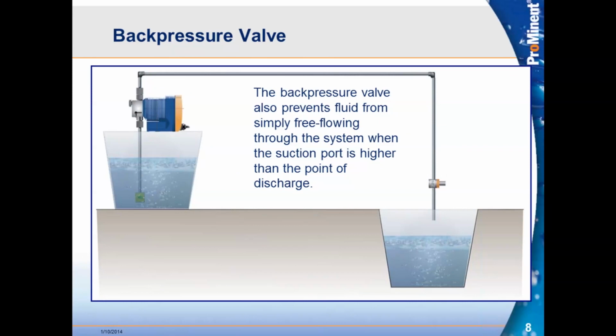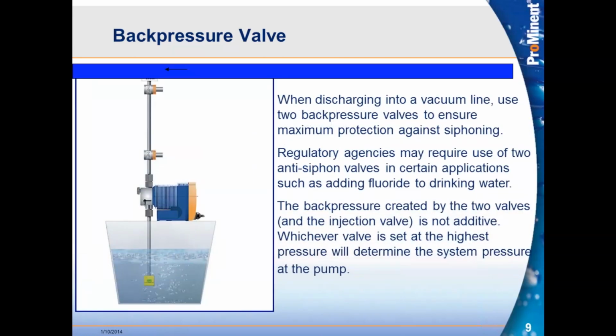So here we're pumping below grade, below where the supply and where the pump is. And of course, that's how we create a siphon. So now we have a back pressure valve all the way over close to the injection point. So we have to be careful, again, not to create a siphon. Sometimes some regulations insist that we have 2 back pressure valves, and they want to be ultimately sure that the chemical doesn't siphon into the process. Fluoride into drinking water is one example. Depending on where you're at in the country, sometimes that regulation is to have a redundant back pressure valve.